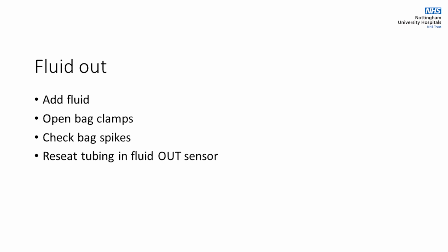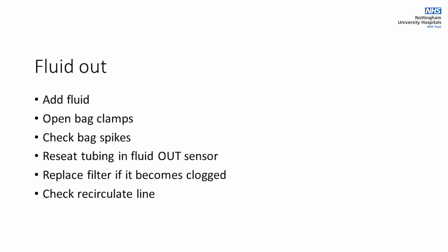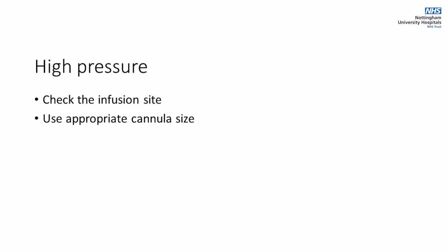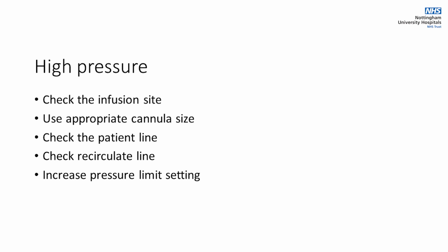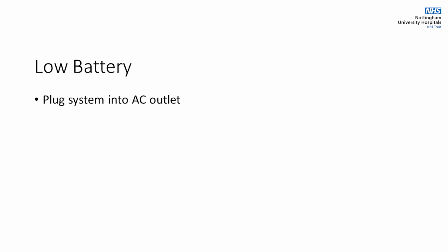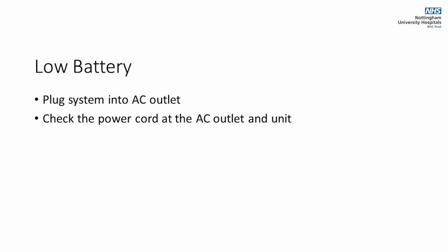Fluid out. Add fluid, open bag clamps, check bag spikes, reseat the tubing in the fluid out sensor. Replace the filter if it becomes clogged and check the recirculate line. High pressure. Check the infusion site, use the appropriate cannula size, and check the patient line. Check the recirculate line. Increase the pressure limit setting. See Chapter 4 of the Operator's Manual. Low battery. Plug the system into an AC outlet. Check the power cord at the AC outlet and unit.